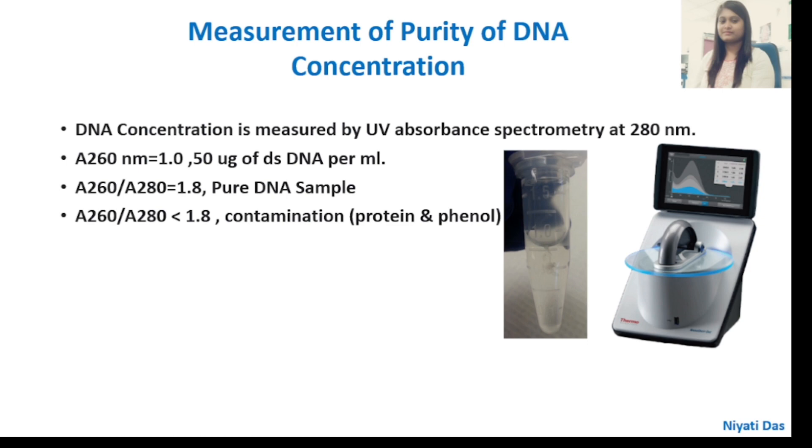We will measure the purity and DNA concentration using UV absorbance spectrophotometry at 260 nm. An absorbance of 1.0 at 260 nm equals 50 micrograms per ml concentration. A 260/280 ratio equal to 1.8 indicates the sample is pure DNA. If the 260/280 ratio is less than 1.8, there is contamination with protein or phenol.